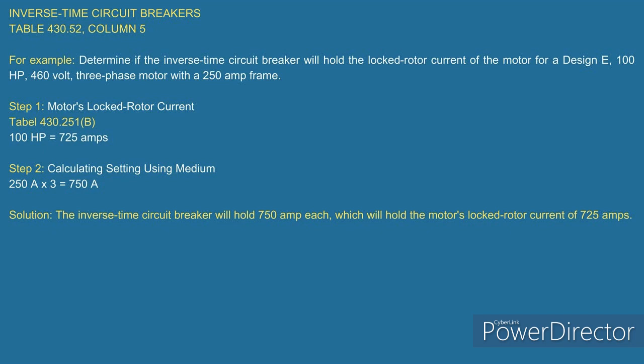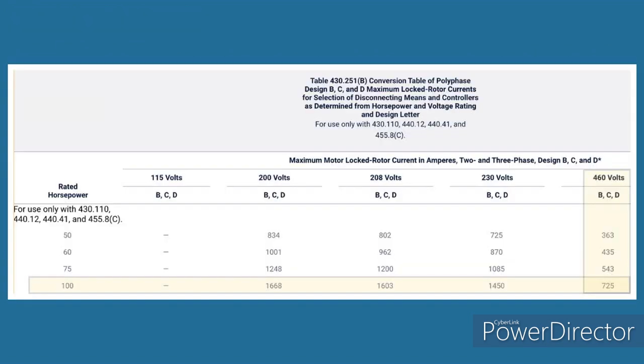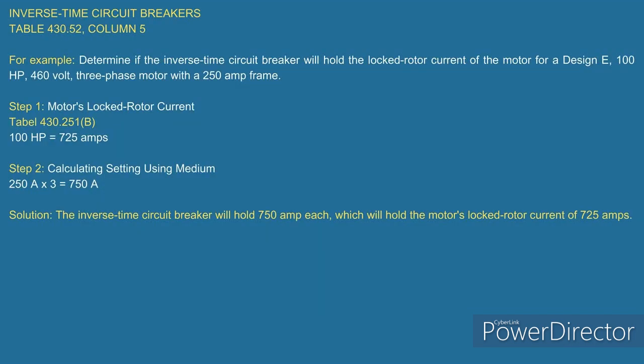Sure. And here's a good example. A while ago we did an instantaneous trip circuit breaker with a 150 amp frame. I'm doing the exact same thing here, but with a 250 amp frame. Same size motor and everything. If I go back and look at my 100 horsepower, it's still 725 amps for the locked rotor current. Then I said you're going to take a circuit breaker usually at what? 3 times. So if I take a 250 amp frame at 3 times, that's going to give me 750 amps. If that was a 150 amp frame, then this inverse time circuit breaker wouldn't have been large enough.